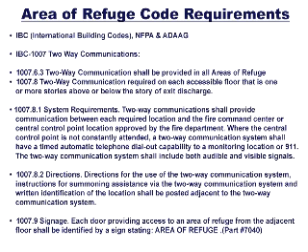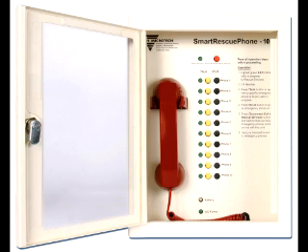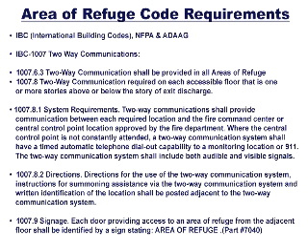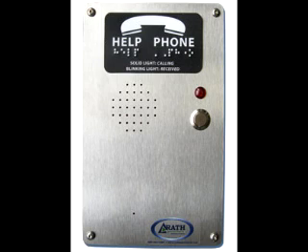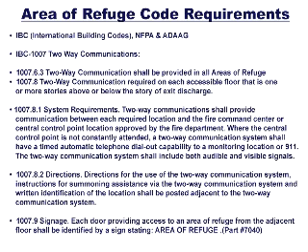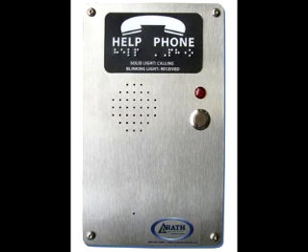Section 1007.8.1, system requirements: Two-way communications shall provide communication between each required location and the fire command center or central control point location approved by the fire department. Where the central control point is not constantly attended, a two-way communication system shall have a timed automatic telephone dial-out capability to a monitoring location or 911. The system shall include both audible and visible signals. Most local authorities having jurisdiction (AHJ) require two-way off-site person-to-person voice communications. Our call boxes will call the base station; if no one answers, they can call up to four different outside phone numbers. A battery backup system is provided for each box in the event of a power outage.